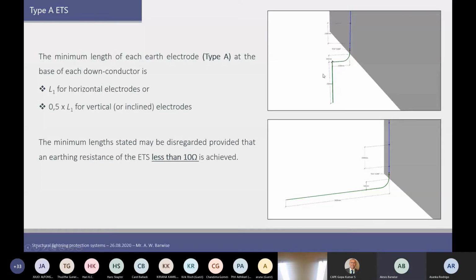And notice also that the standard guides us that this 2.5 or even this 5 meter always has to start at least a half a meter below the contact surface, so the above ground portion. And that's very important because that's part of the earthing system's resistance in order to ensure that you are safe as a human being.